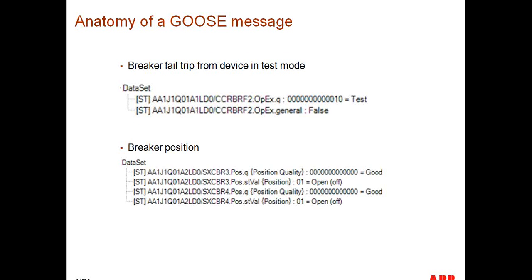Here I just wanted to show a couple of pieces of information shared as part of a Goose message. In this particular case, this is RBRF, my breaker fail function, OPEX.general, which is the actual trip or the operation. The value is false, meaning the function has not operated. Then there's something called the quality. The quality is a series of numbers that contain information about the device that's publishing the Goose message. In this case, the quality indicates that the device sharing this info is in test mode, and we'll discuss towards the end of the presentation why this is so significant.